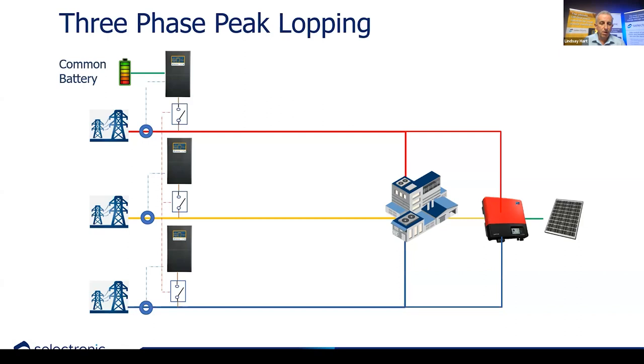So the blue little donut there is a CT, and we've got a contactor in between the bidirectional inverter and the grid supply. Effectively, when the net draw from the grid is under 100 kilowatts, we're going to be charging the battery. If it is over 100 kilowatts, we're going to be discharging the battery into the load to supplement what the load needs without exceeding that 100 kilowatts from the grid. So this has the great flexibility in being able to achieve an increased supply and avoiding some of those charges that we've talked about a little bit earlier.